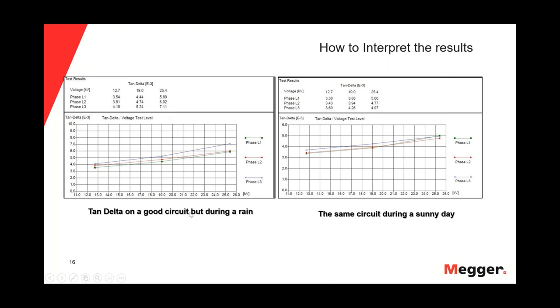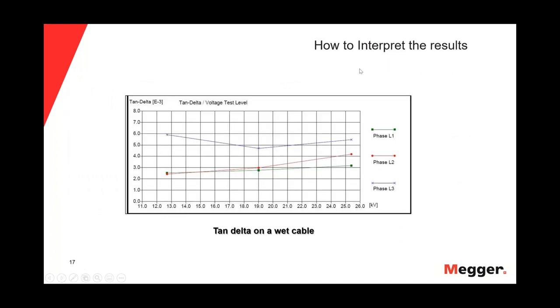How to interpret results with a wet cable: phase one is green, phase two is red, phase three is blue — same scale of Tan Delta and voltage. When the cable is wet, you can see that phase three initially starts high. Then as the voltage is applied and increased, you actually see a decrease, indicating that it is water. That's what this cable shows under an actual wet condition.